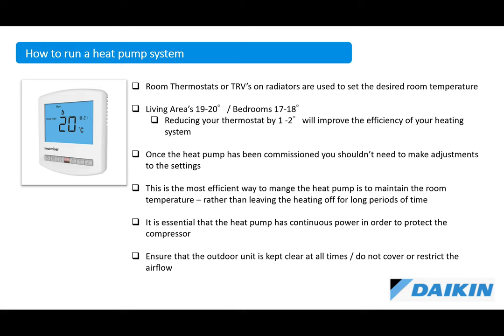If anything like that starts to happen, the heat pump has its own program built in, electronic functions to protect the compressor. And provided that there's always power to the compressor, it's always going to protect itself. And then the other important point is that you keep the outdoor unit clear at all times. You don't put a trellis and some nice trailing shrubs up around the heat pump to cover it because you don't like the look of it. Unfortunately, these are a part of our lives now. We have to keep them clear. We have to allow for the air to circulate freely around.